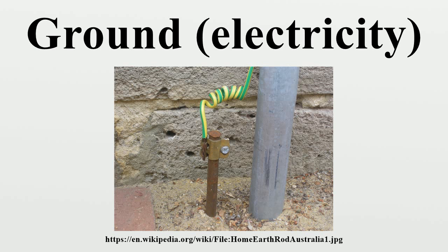An ideal signal ground maintains a fixed potential regardless of how much electric current flows into ground or out of ground. Low impedance at the signal frequency of the electrode-to-earth connection determines its quality, and that quality is improved by increasing the surface area of the electrode in contact with the earth, increasing the depth to which it is driven, using several connected ground rods, increasing the moisture content of the soil, improving the conductive mineral content of the soil, and increasing the land area covered by the ground system.